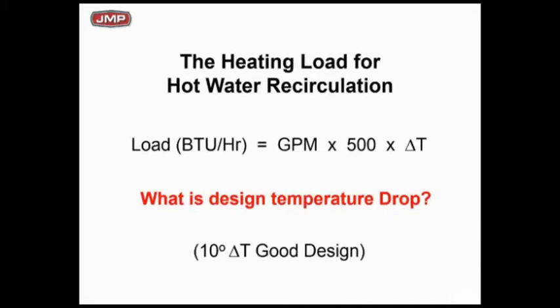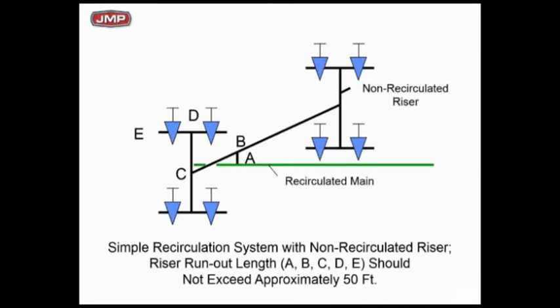First, let's talk about the heat load. We want the heat loss in that supply piece of pipe. It's the familiar formula: Q = GPM × 500 × delta T. The first question is: what is a good design delta T? I'm going to use 10 degrees. 20 would probably work, 5 is okay, but 10 degrees is very reasonable. A lot of designers use 10, but there's nothing cast in stone about that.